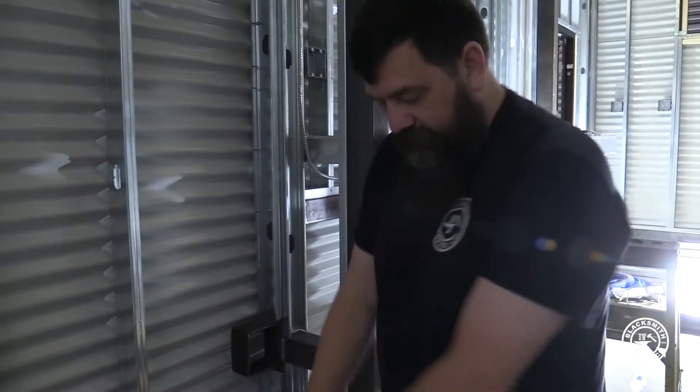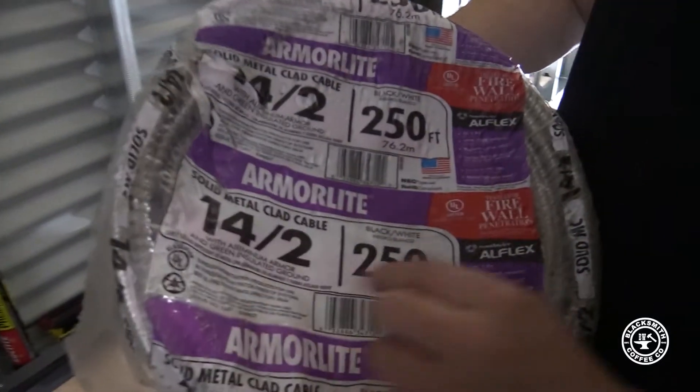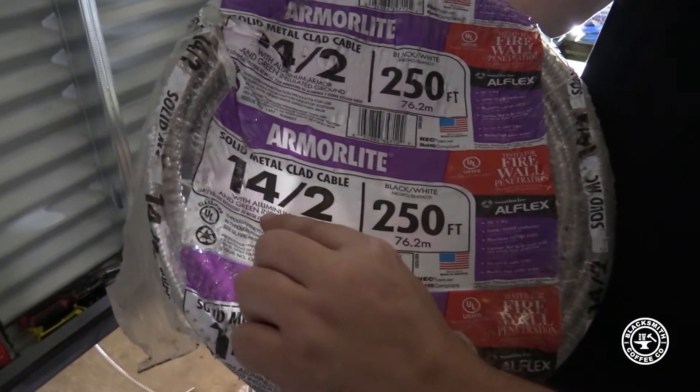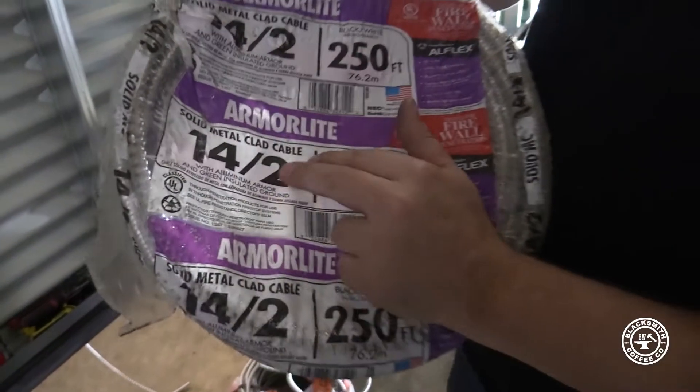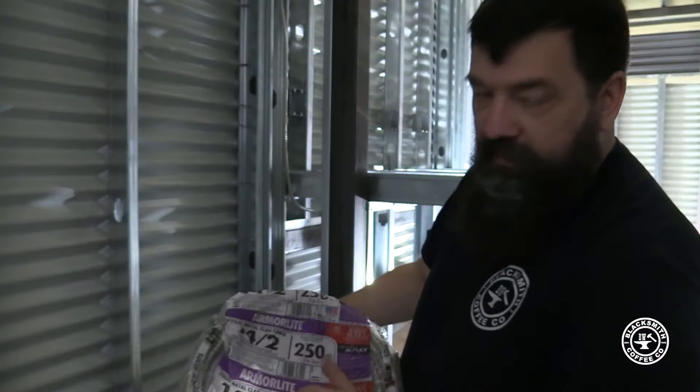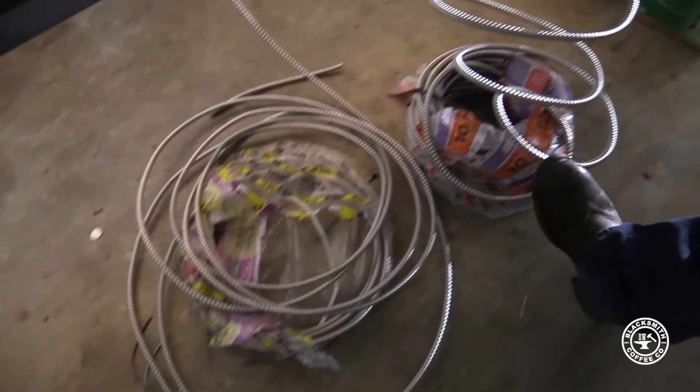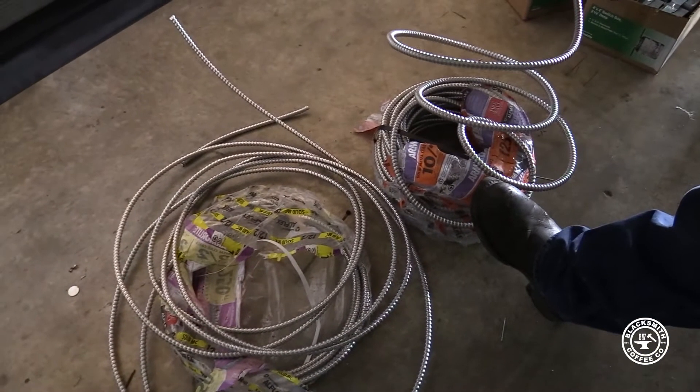It's what's inside that counts, and what it looks like on the package here, see this is 14-2, and then it's going to be with ground. If you read all this, it'll say with a green insulated ground. So this basically has three connectors. 14 means the size, two is how many connectors, and it's with a ground. So 14-2 with ground means it has three wires. This would be 12-2 with ground, and then this is 10-2 with ground.